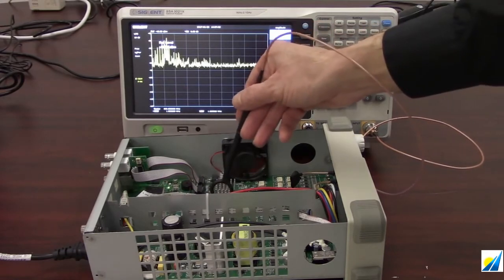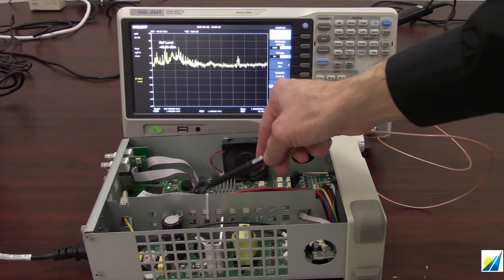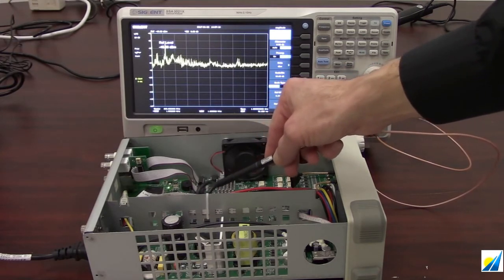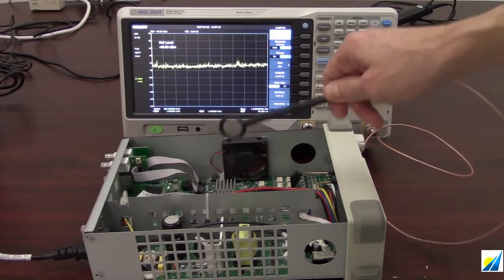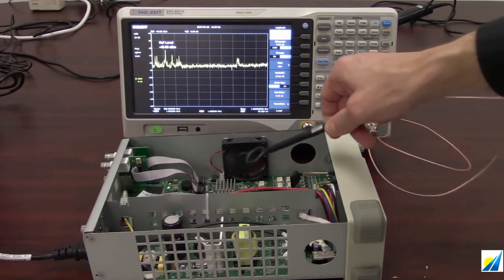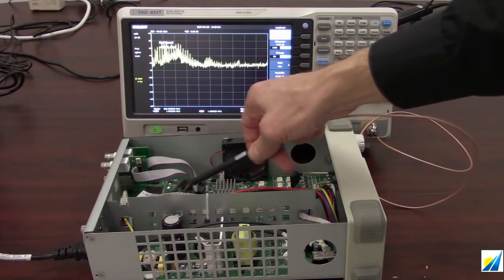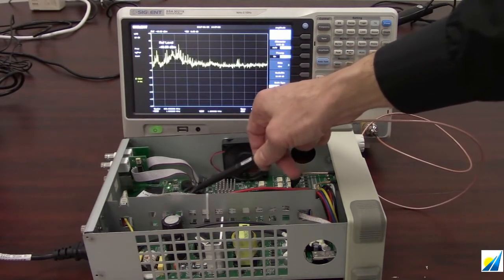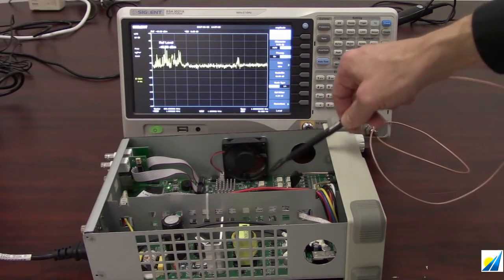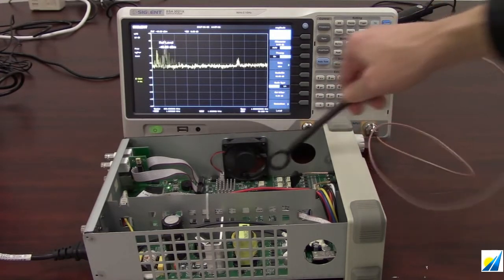This isn't a direct indication of a failure from an electromagnetic compliance test standpoint. The near field probes are typically used for troubleshooting — they're also called sniffer probes. You may already know where your issue lies, and you can sniff out the areas that may be most problematic on your design. The spectrum analyzer with these probes helps you find particular problem areas and make corrections accordingly.